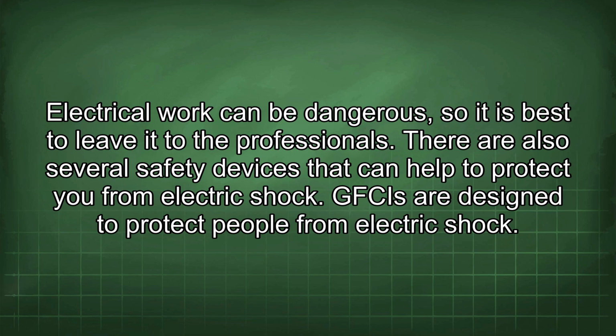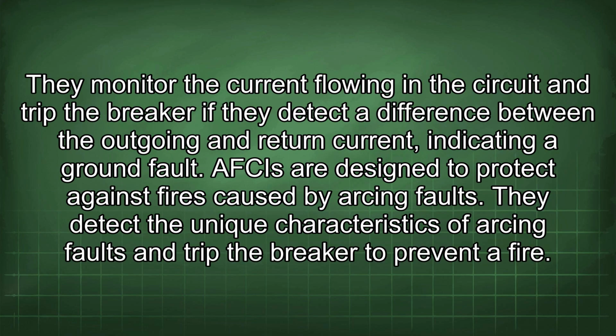GFCIs are designed to protect people from electric shock. They monitor the current flowing in the circuit and trip the breaker if they detect a difference between the outgoing and return current, indicating a ground fault. AFCIs are designed to protect against fires caused by arcing faults. They detect the unique characteristics of arcing faults and trip the breaker to prevent a fire.